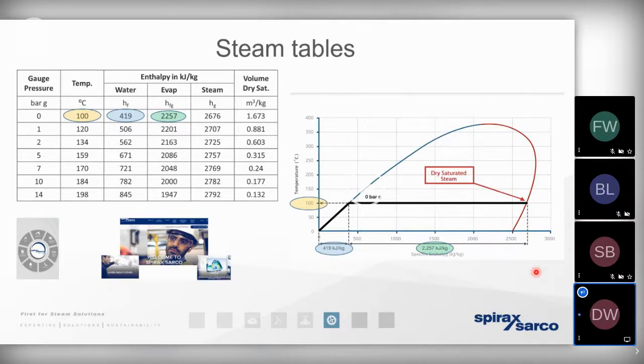For one, it's more likely to condense out in the distribution pipework. And the more heat loss we've got in the distribution pipework, the more condensate we've got generated. And that means that it could well be that we've got a starvation of steam available for the process. For example, if the heat exchanger requires 9,800 kilograms per hour, if we're producing 10,000 kilograms per hour in the boiler, but if we're losing 500 kilograms per hour to the distribution network, then we simply may not have enough steam available to satisfy the process.